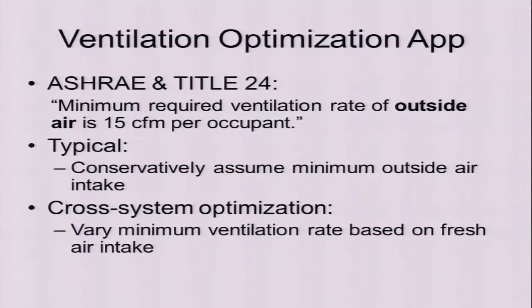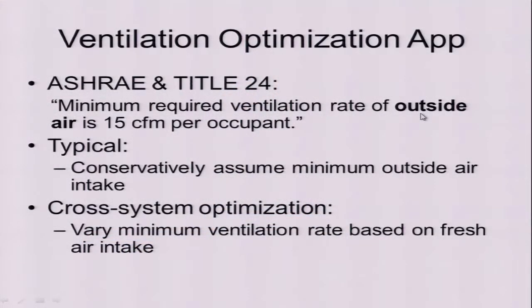Finally, I want to show you what this looks like in practice. I'll talk a bit about this ventilation optimization app we implemented in this building. It's based on the fact that ASHRAE and Title 24 specifies minimum ventilation required for spaces in terms of outside air per occupant and also per square footage. The key parameters are outside air and per occupant. So if you know how much outside air your building is taking in, and/or how many occupants are in the space, you can control the amount of ventilation required.